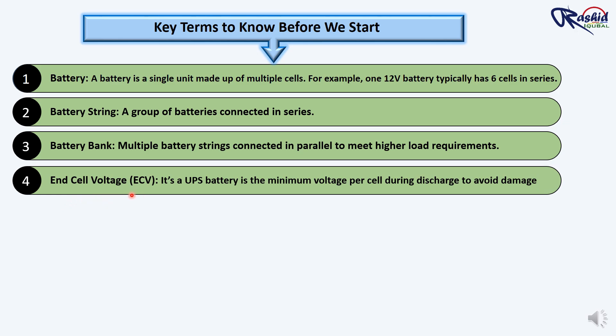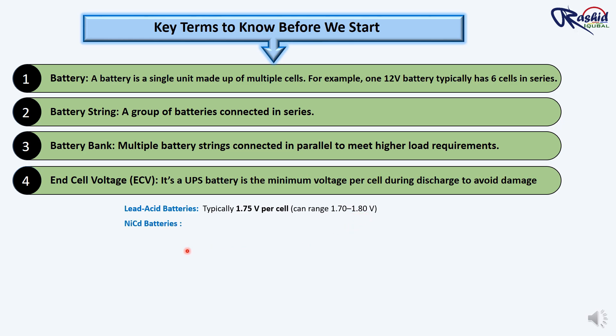Fourth: End cell voltage. End cell voltage is the lowest permissible voltage per cell during the discharge cycle, beyond which the battery should not be discharged. Discharging the battery below this voltage can lead to permanent damage, reduced capacity, and a shorter lifespan. Typical end cell voltages: lead acid battery — 1.75V per cell (range 1.70 to 1.80V); nickel-cadmium batteries — 1.0V to 1.1V per cell.